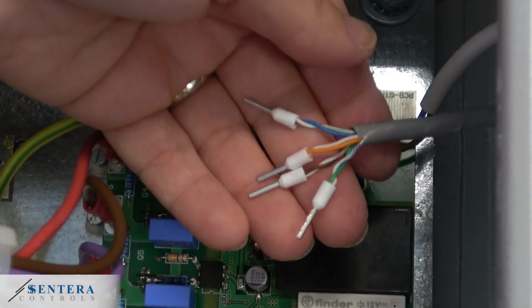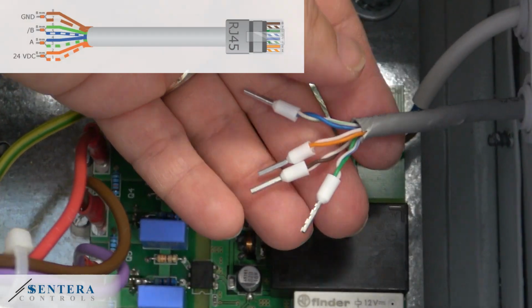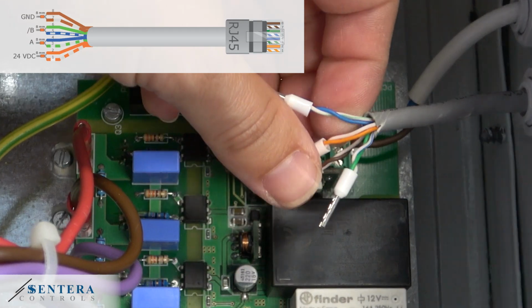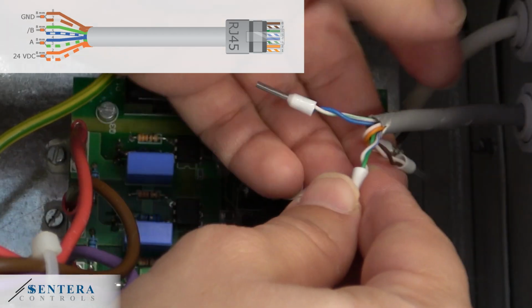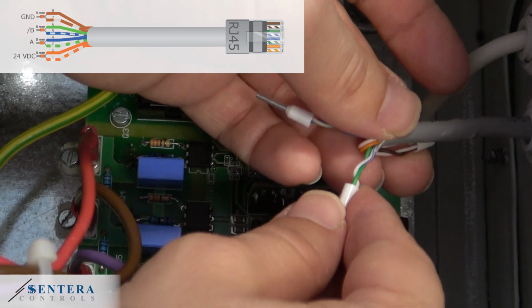If you want to use the complete set of possibilities and options offered by the GTH series, you need to connect it to Modbus. I'm going to show you how. To control the GTH using our free Modbus software, the 3SModbus, you will need a UTP cable that's crimped on one side with the RJ45 socket with loose wire ends at the other side. You only need to connect the A and B signal. The other two, the power supply and the ground, you do not need to connect. You should either isolate or cut them.